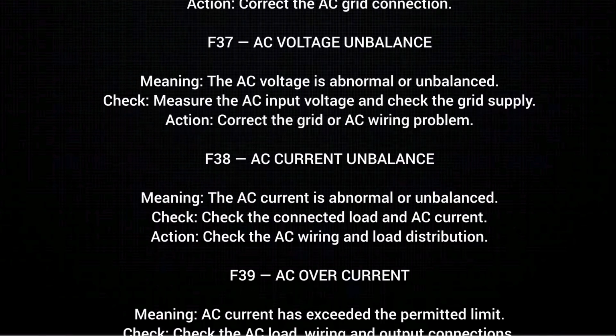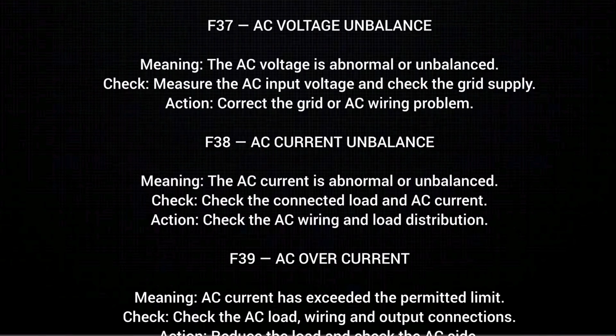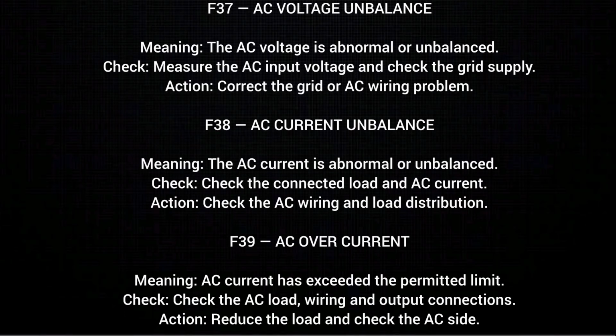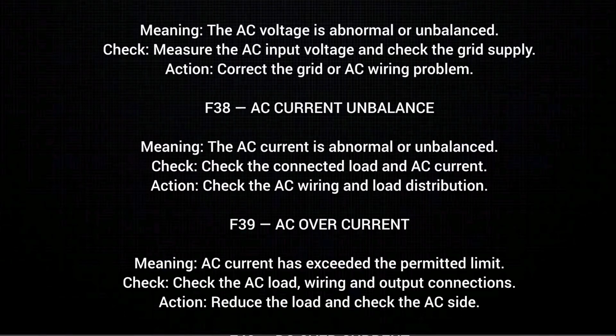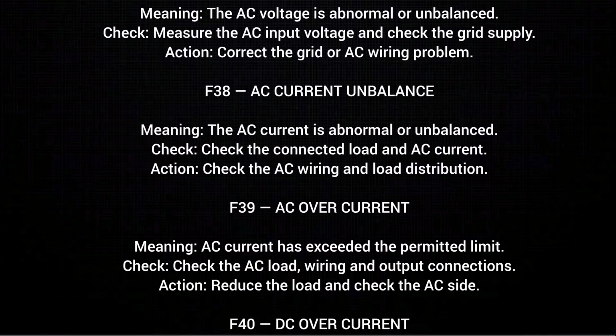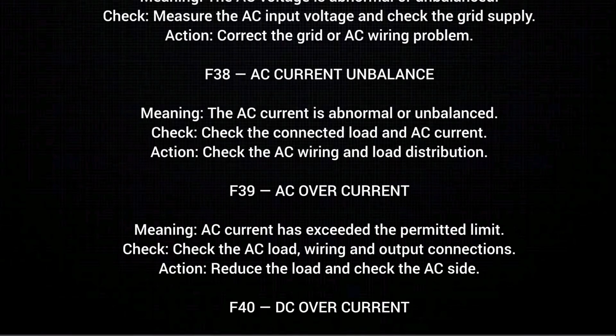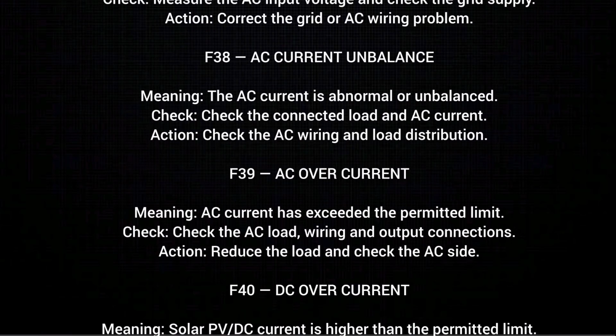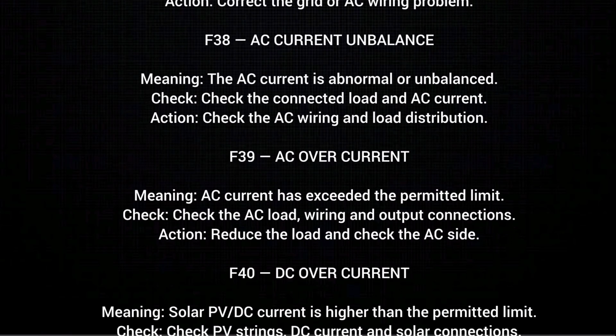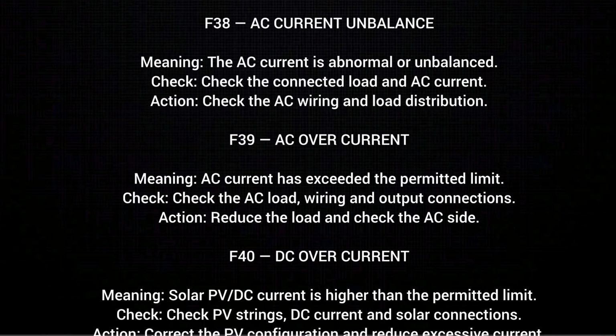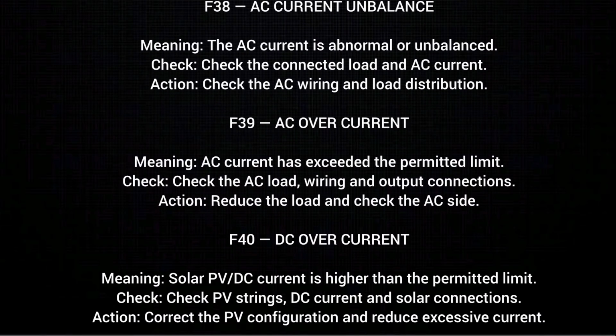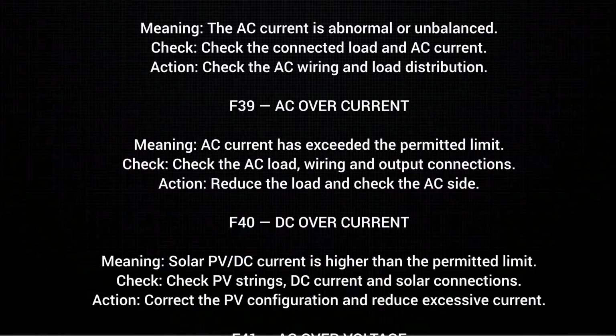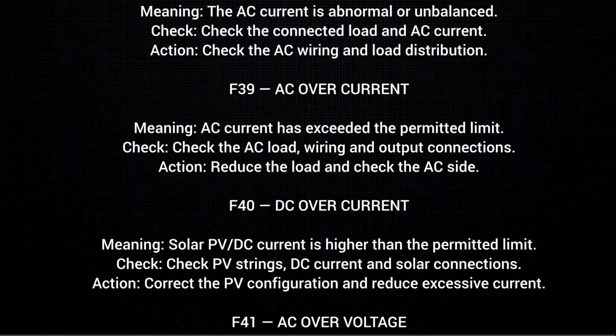F38. AC current unbalanced, meaning the AC current is abnormal or unbalanced. Check. Check the connected load and AC current. Action. Check the AC wiring and load distribution. F39. AC overcurrent, meaning AC current has exceeded the permitted limit. Check. Check the AC load wiring and output connections. Action. Reduce the load and check the AC side.